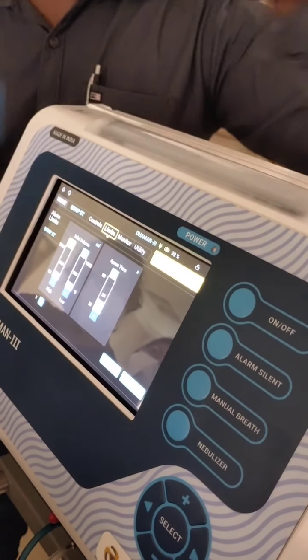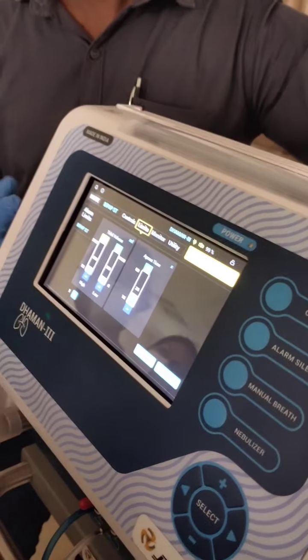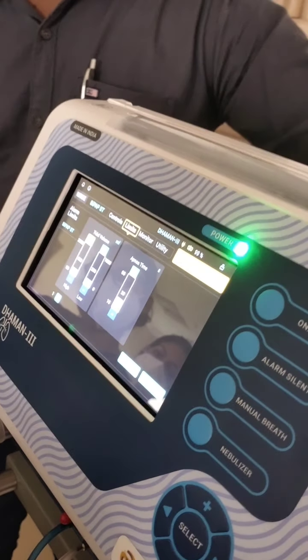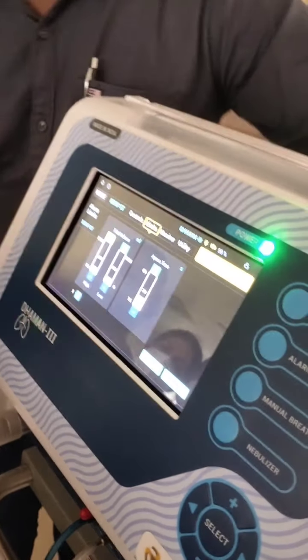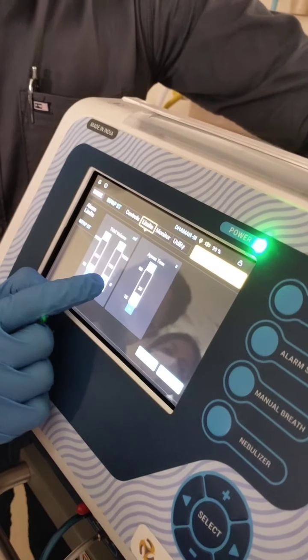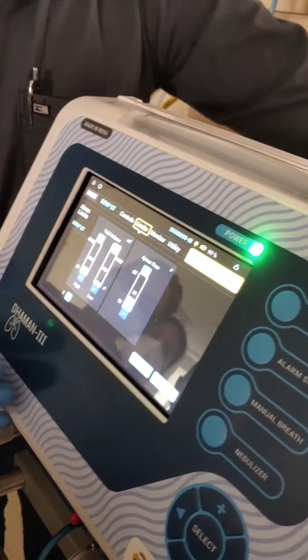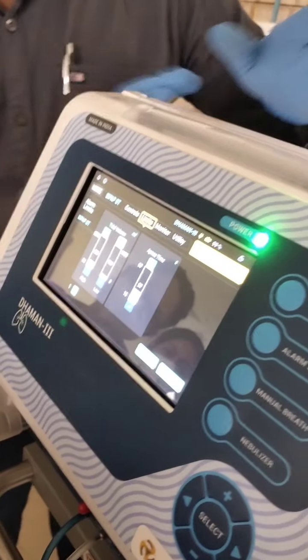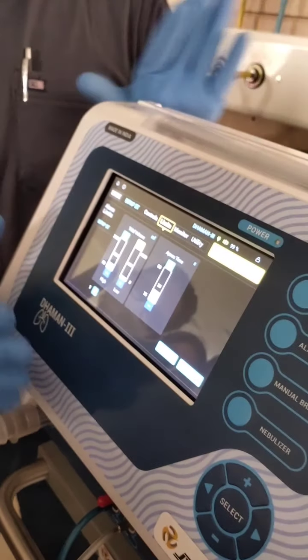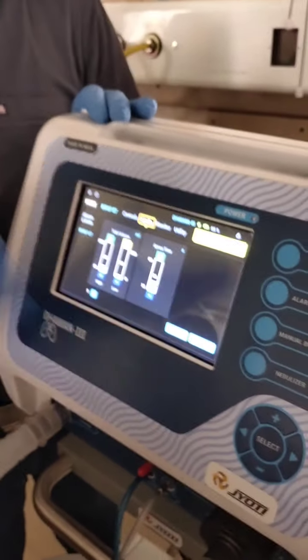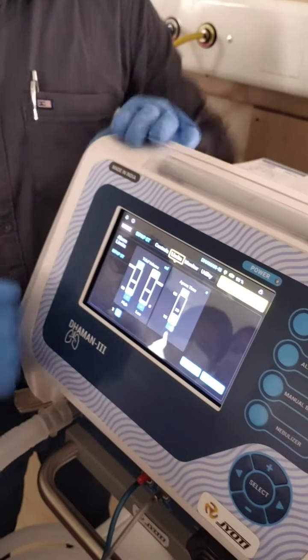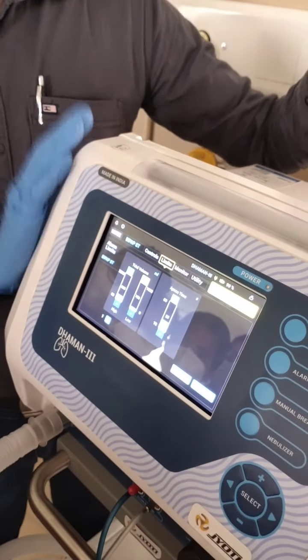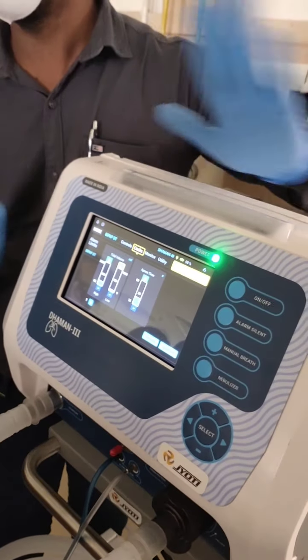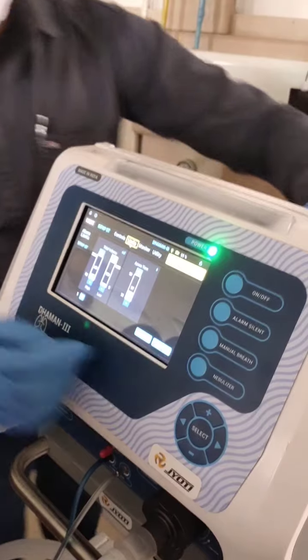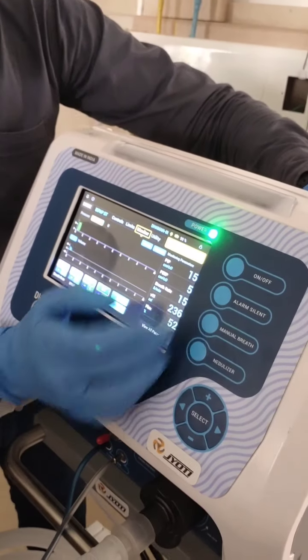So if the 200 value is varying, what will happen? The low minute volume or high minute volume error will come. So I have to reduce the tidal volume. So 100, for the default value, I reduced to that point. This is not a simple thing for the alarm, not that the alarm is switched on. For that, before we set the value, in that set value we have to reduce the alarm limit. That's why we are using it. Nothing apart from the patient alarm. Okay, so now I confirm, and yes.